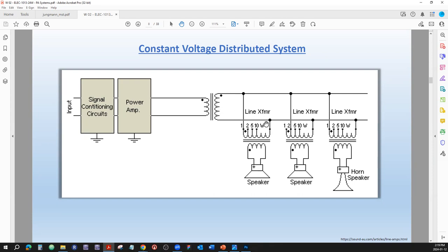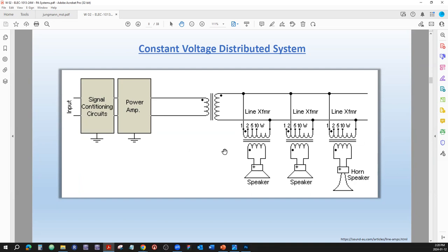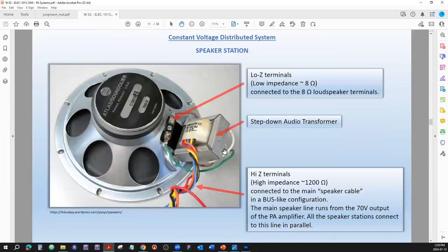That gives us a lot of freedom in connecting. If all speaker stations are tapped at 1 watt and the amplifier produces 200 watts, you can connect 200 of those stations — you just add up the wattage consumed by each station.